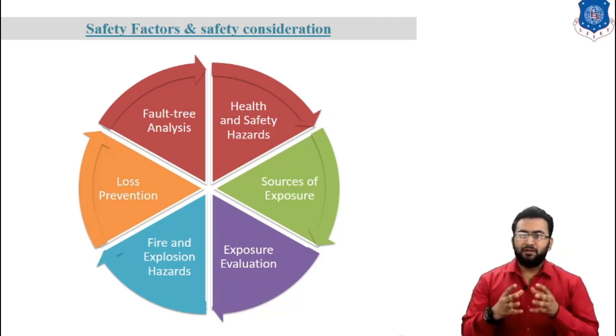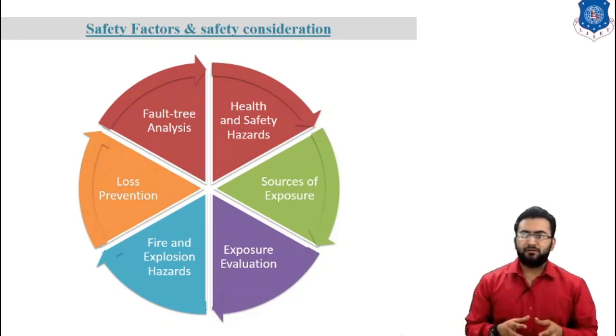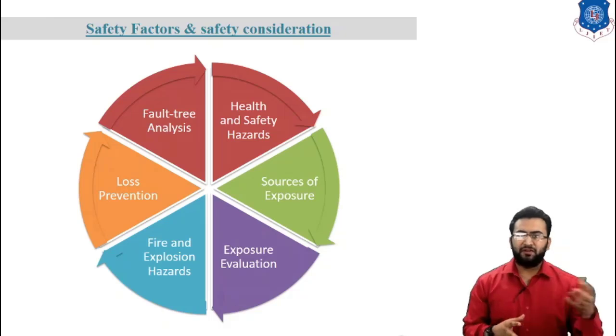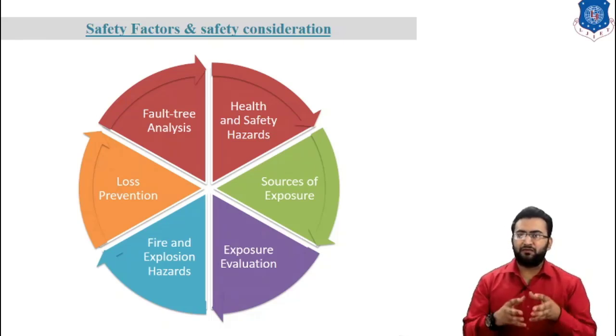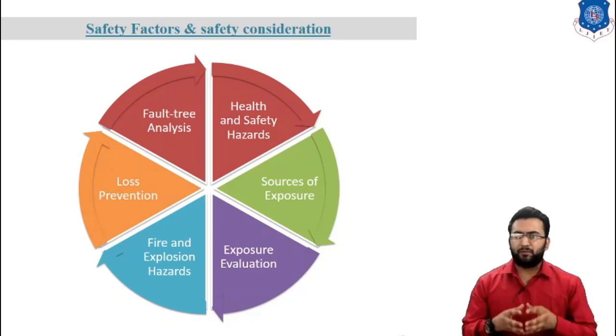The safety factors represent the amount of over-design that would be used to account for the change in operating performance with time. The application of a safety factor can be very detrimental to the design. Each piece of equipment should be designed to carry out its necessary function. If uncertainties are involved, a reasonable safety factor can be applied. The role of a particular piece of equipment in overall operation must be considered along with the consequence of under-design.